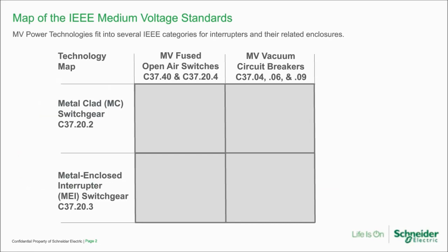Here's a map of the IEEE world of medium voltage switchgear. Medium voltage power technologies fit nicely into several categories — some for interrupters and some for their enclosures. Until the 1990s, this worked out pretty well; then the lines began to blur. Reading down the left side of the map, you see the enclosures: on the top is metal clad (MC) switchgear defined by C37.20.2, and on the bottom left is metal enclosed interrupter switchgear (MEI) defined by C37.20.3. Reading across the columns, C37.40 is for power fuses and C37.20.4 is for switches — 1 kV to 38 kV used in metal enclosed switchgear.